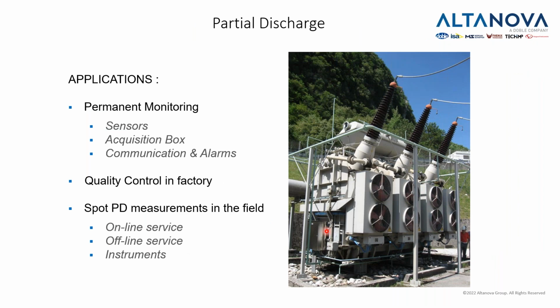Well, we do it always in the factory after the transformer has been produced, and we also do it in the field. In the field, we can do online or offline tests. Online means that we are using the voltage of the network, and offline test means that we have brought a source and we will energize the transformer. Online is much easier to do and much cheaper. Offline has some possibilities which online doesn't have.